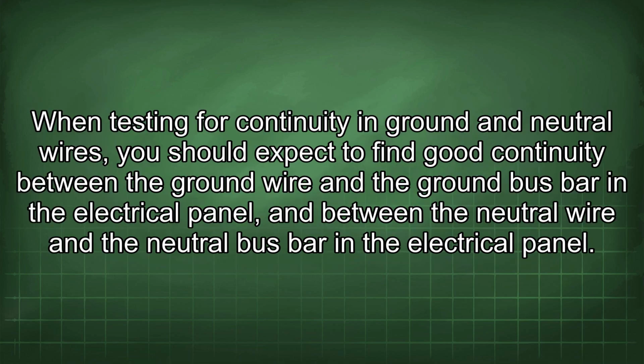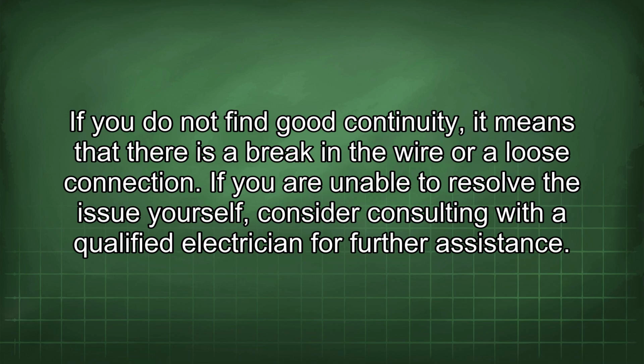When testing for continuity in ground and neutral wires, you should expect to find good continuity between the ground wire and the ground bus bar in the electrical panel, and between the neutral wire and the neutral bus bar in the electrical panel. If you do not find good continuity, it means that there is a break in the wire or a loose connection. If you are unable to resolve the issue yourself, consider consulting with a qualified electrician for further assistance.